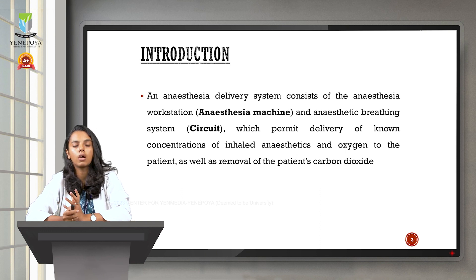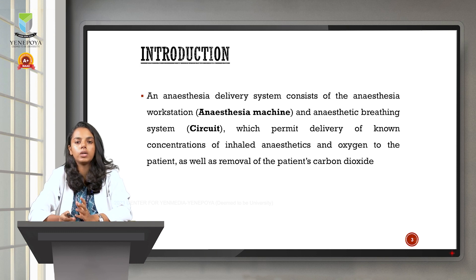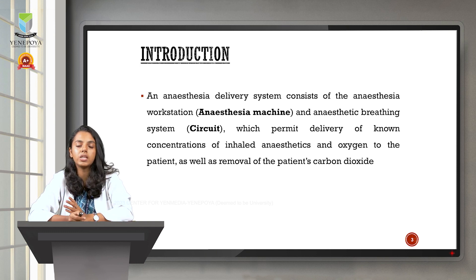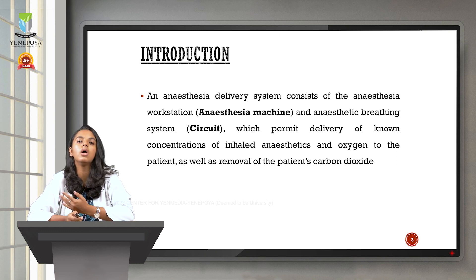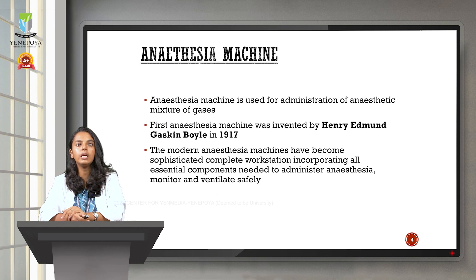Since the patient is anesthetized, the patient won't be breathing voluntarily, so we have to provide the breaths — both inspiratory breaths and promote expiration. The anesthesia machine gives oxygen mixed with the anesthetic gases to the patient, and it is the function of the anesthesia machine to remove the carbon dioxide produced by the patient's body. It is a device used to administer the anesthetic mixture of gases in a known concentration to a patient who is planned to undergo a surgical procedure.